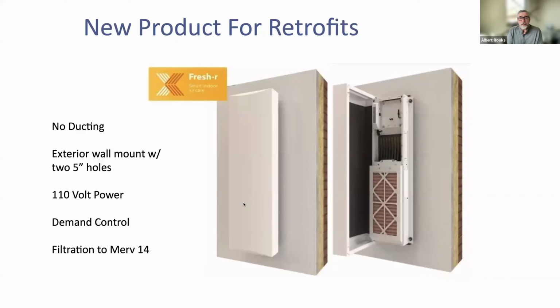So first thing we're looking for in this application is no ducting, right? That's our challenge of multifamily buildings. It's got to be easy to install. And this one takes 2 5-inch holes in the exterior wall. So it mounts on an exterior wall with 2 5-inch holes. It only needs 110 volt power, whereas that nice little CA70, I think we can do that with 110 volt power. Typically that Zehnder stuff needs 220, but I think that one will take 110. So I'm going to leave it at that. And this one, rather than setting the speed, this one's demand control. We'll get into that for a minute.